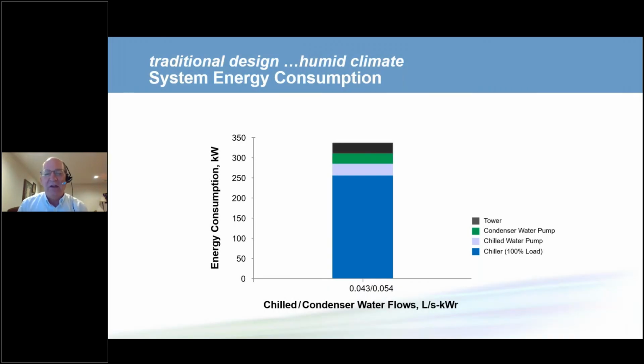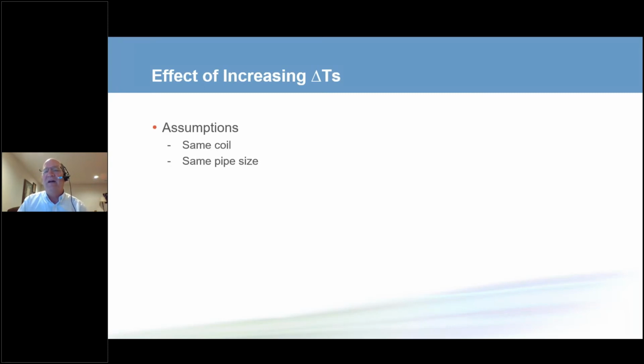So if we look at design conditions of the normal performance chilled water systems, here's our chiller usage at full load, our chilled water pump, condenser water pump, and cooling tower fans. Now, if we followed the recommendations in the ASHRAE GreenGuide and reduced our flow rates and increased the temperature difference, we have to make sure we share the assumptions. The assumptions for this first part are we're going to use the same coil. We'll talk about that in a few minutes. And we're going to use the same pipe sizes, so the pressure drops and pump power will go down. So as the flow is reduced, the pump power goes down. And also, since the pipes are the same size, the pressure drop goes down, so the pump power is reduced.